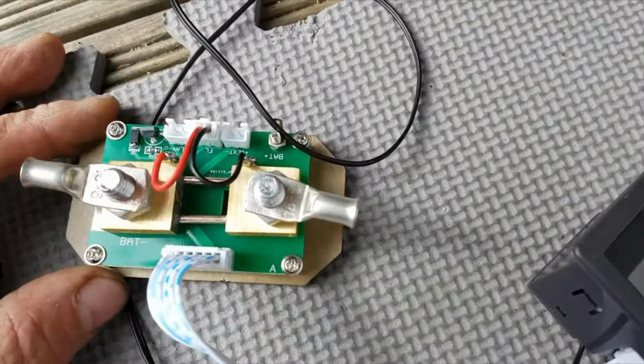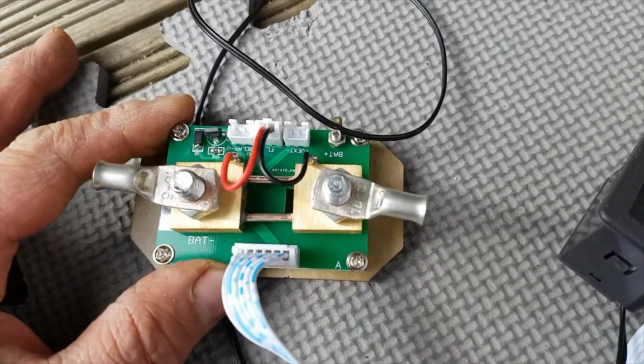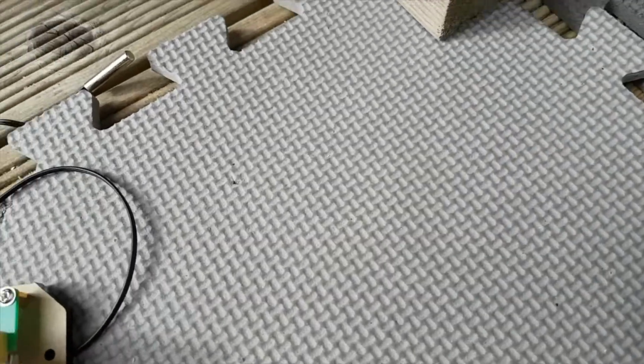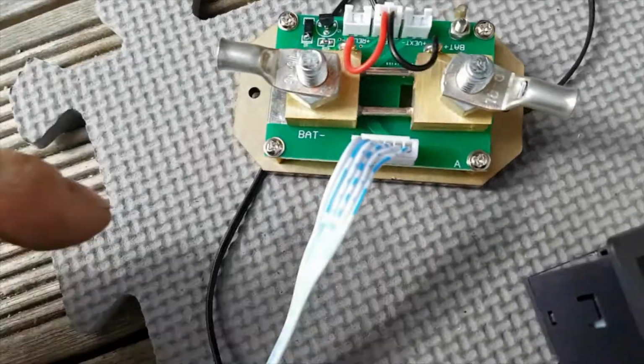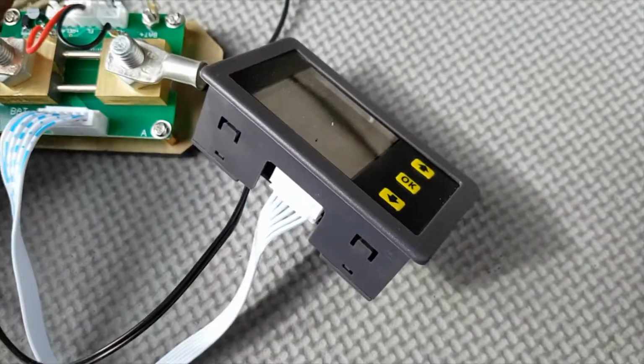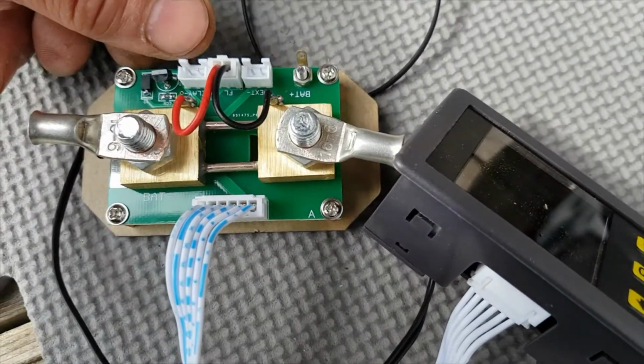So the idea is to use a more conventional shunt type current meter. This shunt is designed for 100 amps. It also has a temperature input on this one, which the other one doesn't have. It uses connectors for the outputs, the relays.